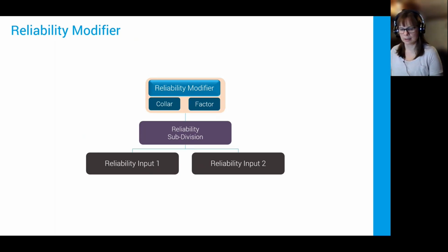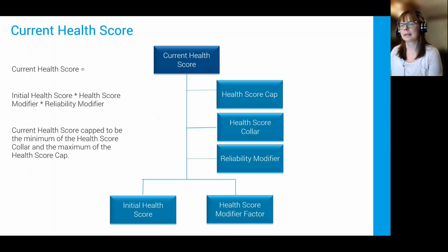Quite often we see something like a particular model of assets or a particular bad batch of assets between particular serial numbers, or certain assets which are just starting to fail, but they're not really captured anywhere else. Reliability is the place that you can add those in. It's almost freely available, but it's the important catch-all if there's anything else relating to condition.